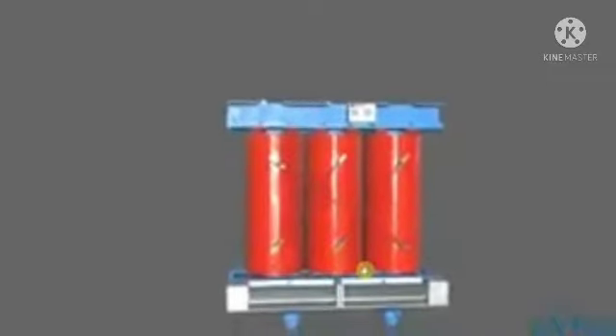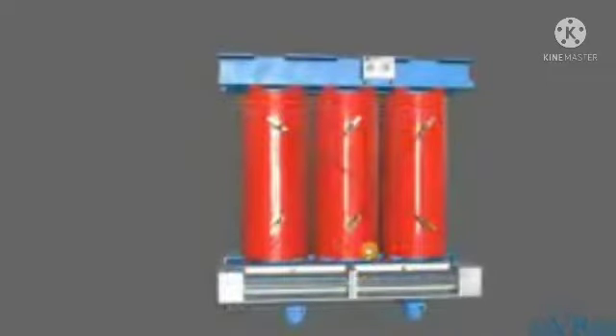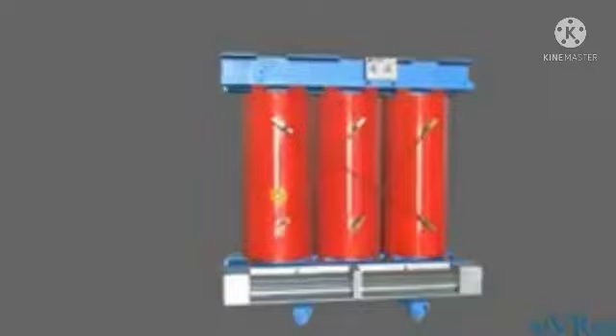The windings themselves are going to be made of copper or aluminium. Aluminium is usually used if there is no consideration to space. If you have a lot of room, you can use an aluminium type transformer. Generally, they'll be bigger than transformers that use copper for the windings. This is because the conductivity of copper is higher than aluminium, and their ability to carry current is also higher. However, aluminium is cheaper, and if you've got the space, then you can install a transformer with aluminium windings.